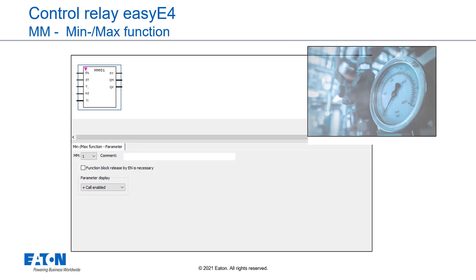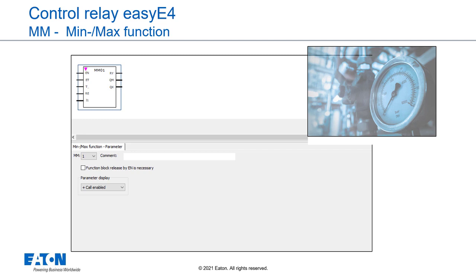easyE4 base devices provide 32 min-max function blocks, MM for short. The function blocks can be used to determine the maximum and minimum values of a changing analog value which is applied to function block input I1. This makes it easy to determine the level of pressure fluctuations in a system for example. If the function block is enabled, the current value at the function block input I1 is compared with the existing minimum value and maximum value. If the current value falls below or exceeds these values respectively, it will accordingly be set as the new minimum value or maximum value. Only one minimum value and one maximum value will be stored in the function block at any one time.